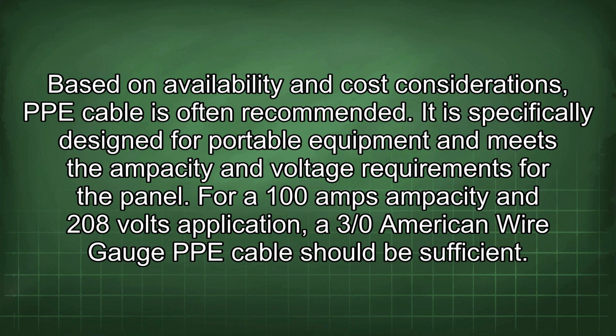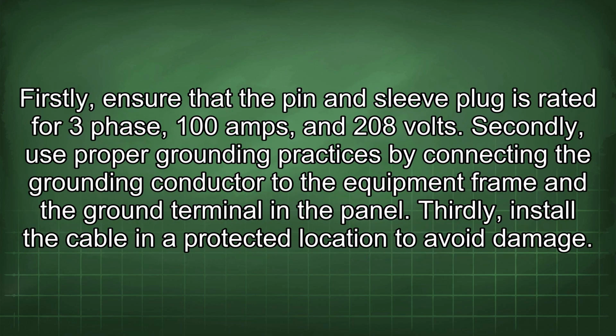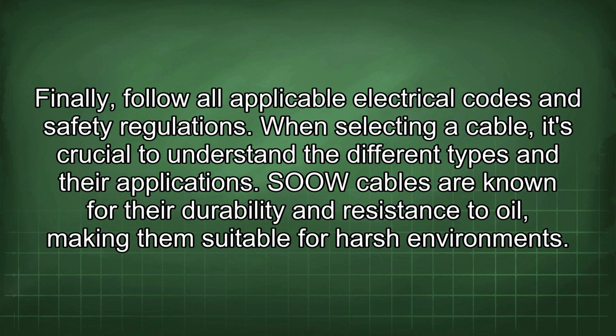It is specifically designed for portable equipment and meets the ampacity and voltage requirements for the panel. For a 100 amps ampacity and 208 volts application, a 3/0 American wire gauge PPE cable should be sufficient. Firstly, ensure that the pin and sleeve plug is rated for 3-phase, 100 amps, and 208 volts. Secondly, use proper grounding practices by connecting the grounding conductor to the equipment frame and the ground terminal in the panel. Thirdly, install the cable in a protected location to avoid damage. Finally, follow all applicable electrical codes and safety regulations.